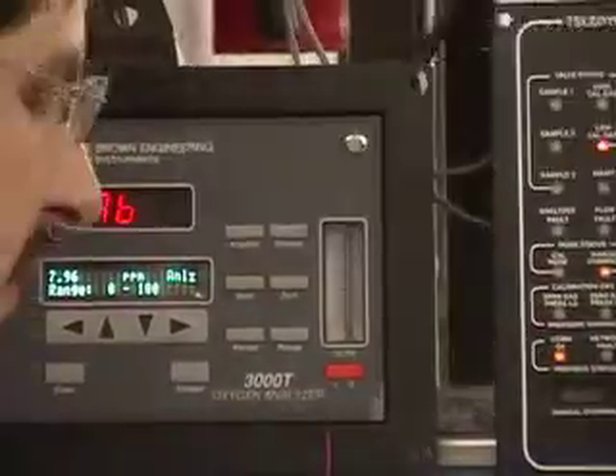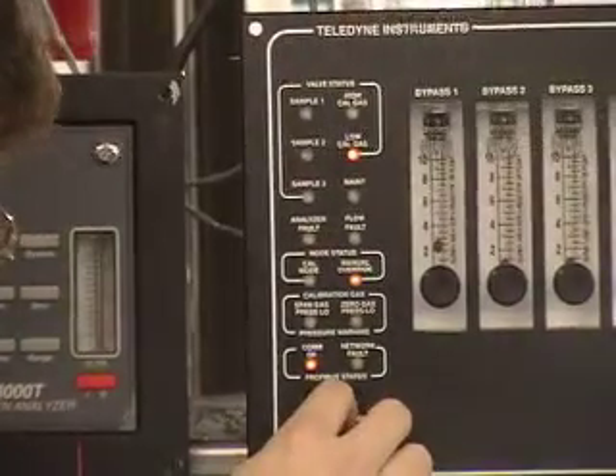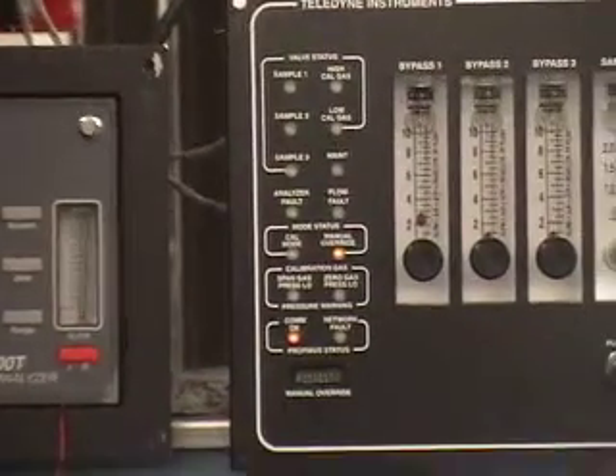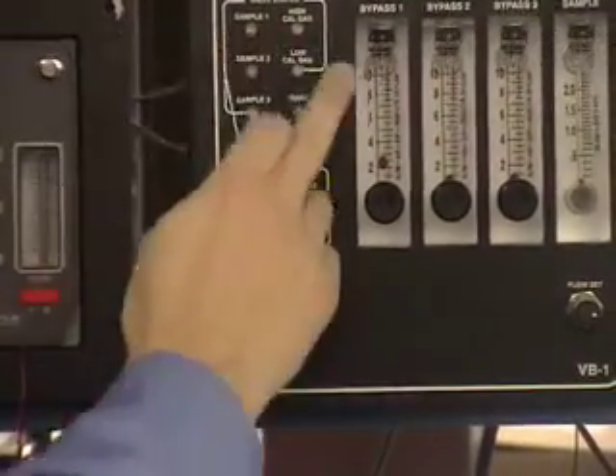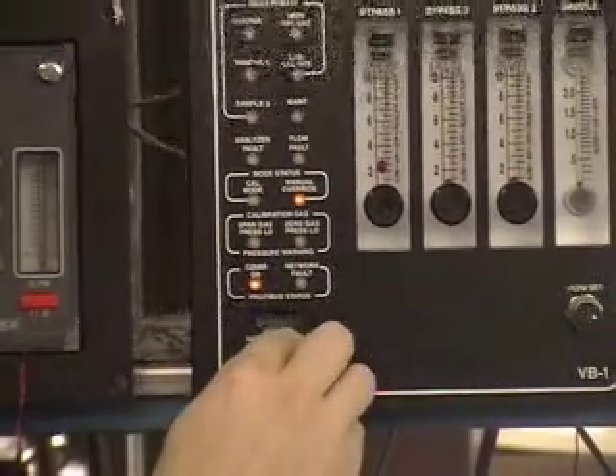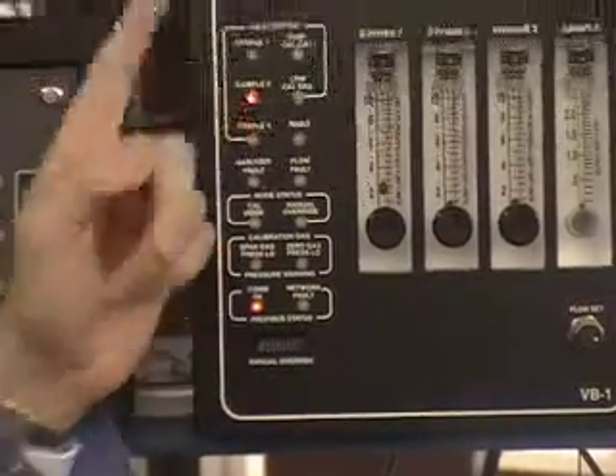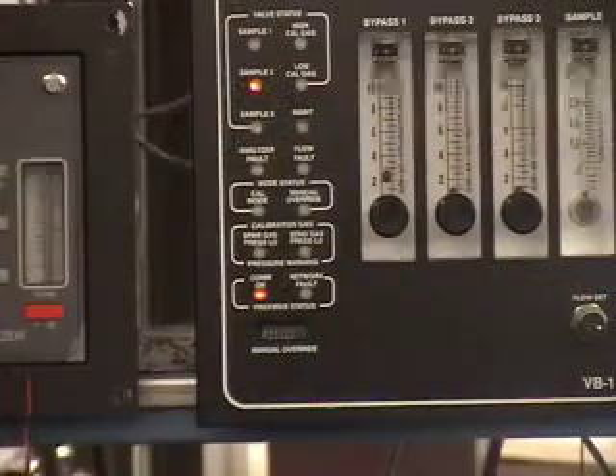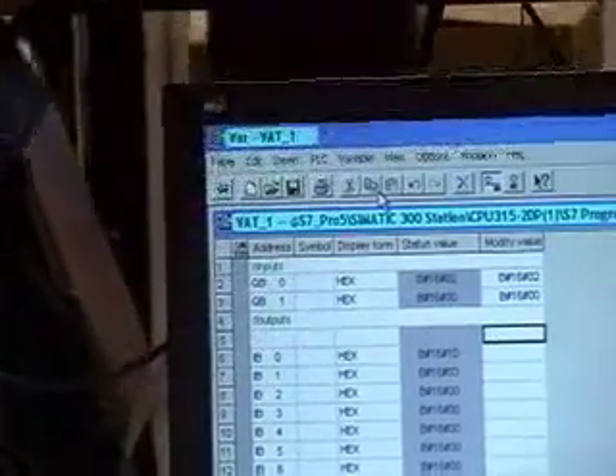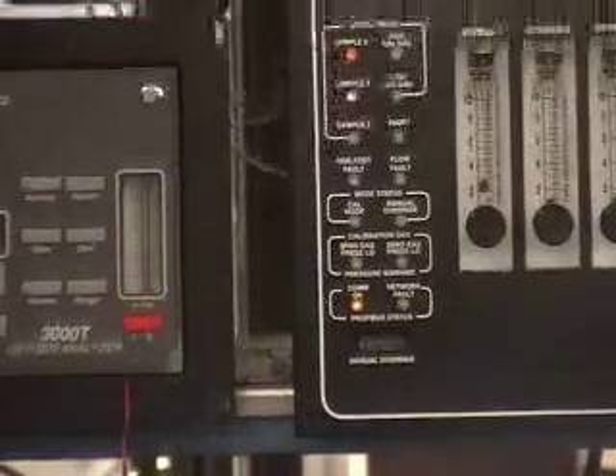There's the zero valve. Okay? So that's the manual override. And you basically disable manual override again. So I move all the switches down, no valve is open. But I'm gonna now disable manual override. And immediately it contacted the PLC to see what command was in the register, in the address, and it was telling it to go to open sample 2. That's where it went to. Okay, that's manual override.